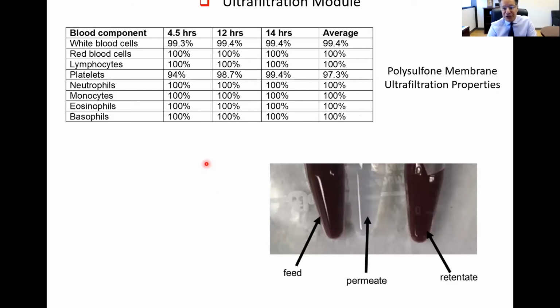So just to show you some of the functionality of these different components, this is the ultrafiltration module. And initially, when we were devising it, we used a polysulfone membrane. And these are just some of its ultrafiltration properties, looking at the different components of blood. And the rejection, this is showing the lack of filtration at different time points. And you can see that it was rejecting the cells from getting through quite well. And this is just a pictorial view of that. This is the blood coming in. This is what comes through the membrane. And it looks clear because there's no red cells. And then this is what didn't get through the membrane and would be returned to the so-called venous side of the device.